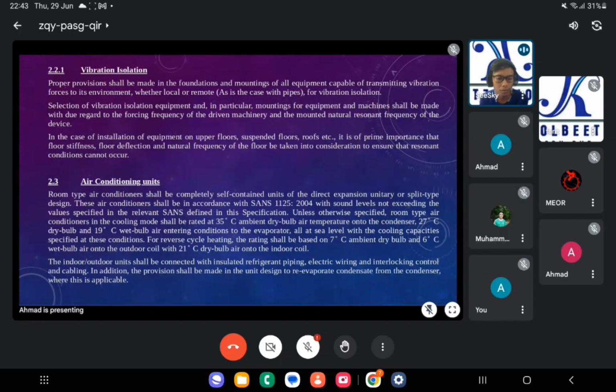Room type air conditioner shall be a completely self-contained unit of the direct expansion unitary or split type design. This air conditioner shall be in accordance with SANS 1125 2004, with sound level not exceeding the value specified in the relevant SANS defined in its specification.